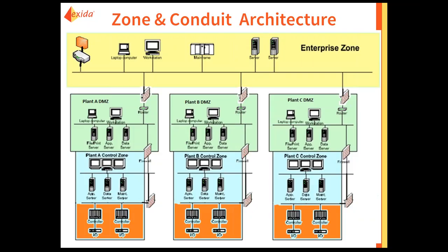From the plant control zone it's allowed to talk to the DMZ. From the enterprise zone they're also allowed to talk to the DMZ. But the router and firewall combination does not allow the control zone and enterprise zone to communicate directly. This is a much cleaner architecture: you have zone separation, firewall-controlled traffic, routing to known destinations, and end devices receiving only the protocols they need.